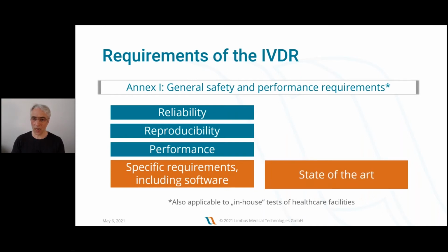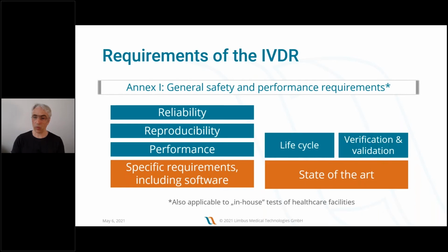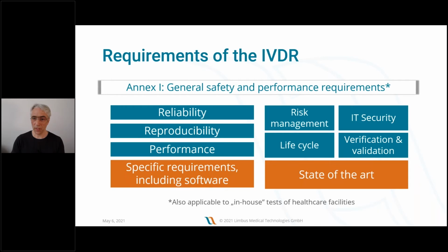Anyhow, software is now addressed with very specific requirements. You have to comply with the state of the art. You have to have processes concerning the life cycle of software. You have to perform verification and validation, perform risk management, and also IT security is mentioned.